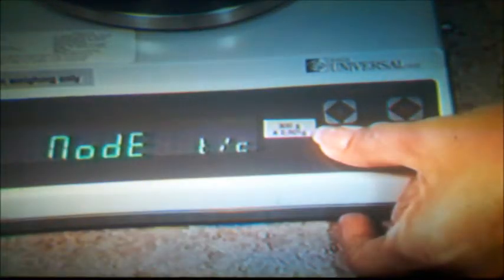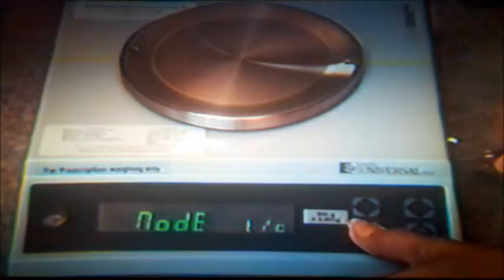Press the T button. You will notice the display change from mode T/C to mode G. Remove your finger from the T button. The display will change to 0.000 G. You are now in the weighing mode. Insert the calibration key into the lower hole on the machine side. You will hear the micro switch. While holding the key against the micro switch, press and hold the T button.